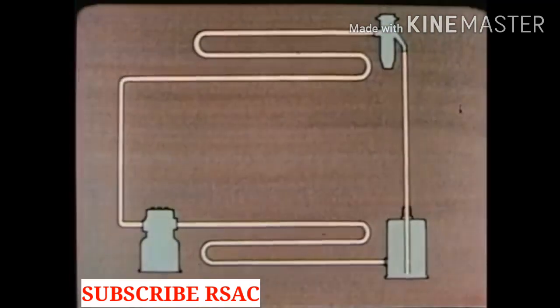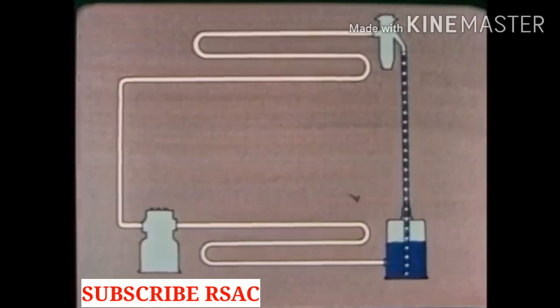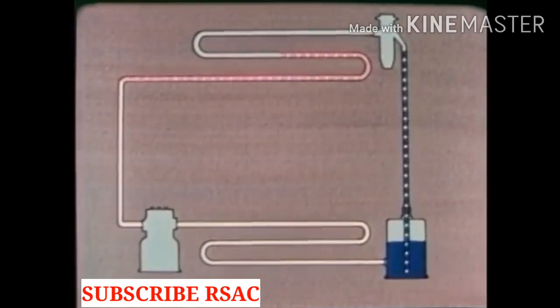Now let's review the whole thing. Refrigerant under high pressure flows from the receiver to the expansion valve. The valve causes a pressure drop. The evaporator takes in heat from the box. If anything in the box is hotter than the refrigerant it gives up its heat to the refrigerant. As the refrigerant takes in heat it changes from a liquid to a gas.